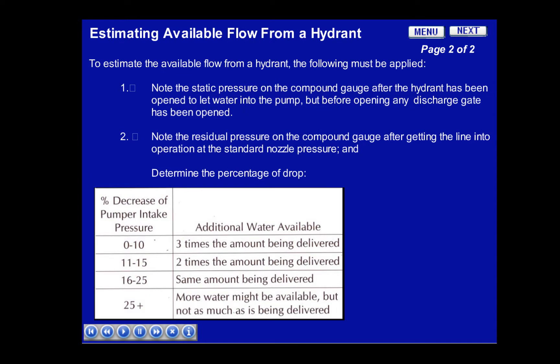Estimating the available flow from a hydrant. To estimate the available flow from a hydrant, the following must be applied: Note the static pressure on the compound gauge after the hydrant has been opened to let the water into the pump, but before any discharge gate has been opened. Then, note the residual pressure on the compound gauge after getting the line into operation at the standard nozzle pressure, and this determines the percentage of the drop.